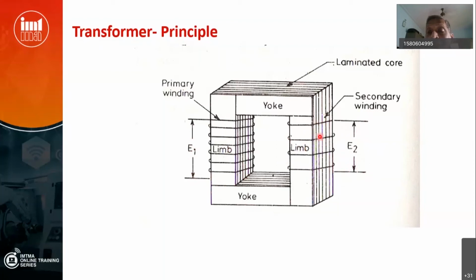Now instead of 10, I made it another 10, 20 turns, connected in series. In this 10 turns also, the same voltage is induced. Another 10 turns, there also again the same voltage. When I connect them in series, 10 plus 10, 20 turns, double the voltage will be available in the secondary. I am stepping up from here to here. When it comes to the receiving station in large load centers, again there are transformers where this side winding turns will be less and this side winding will be more. It will be stepping down.